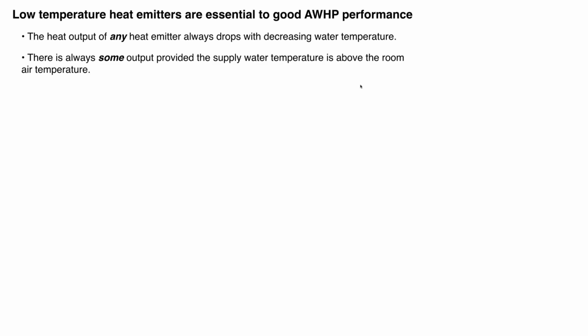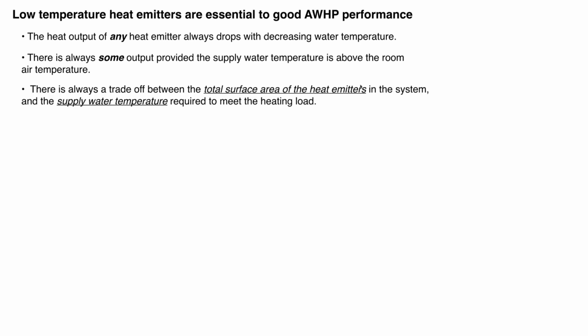That's the fundamentals of heat transfer. But there's always some output as long as that supply water temperature is above the room temperature. I put that one in there because I've had a couple people over the years say, well, John, don't you know that fin tube baseboard stops working below 140 degrees Fahrenheit water temperature? No, it doesn't. The rating table in the literature doesn't go lower than 140, but as long as there's a temperature difference between the water in the tube and the room air, there's going to be some heat transfer, okay?